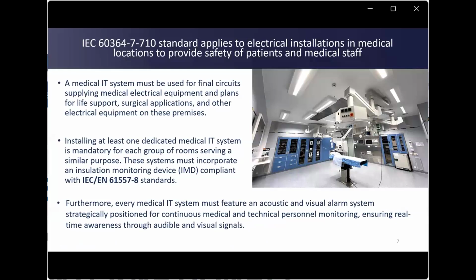The IEC 60364-7-710 standard applies to electrical installations in medical locations to provide safety to patients and medical staff. A medical IT system must be used for final circuits supplying medical electrical equipment, and systems for life support, surgical applications, and other electrical equipment in the premises. Installing at least one dedicated medical IT system is mandatory for each group of rooms serving a similar purpose. These systems must incorporate an insulation monitoring device compliant with IEC EN 61557-8 standards.